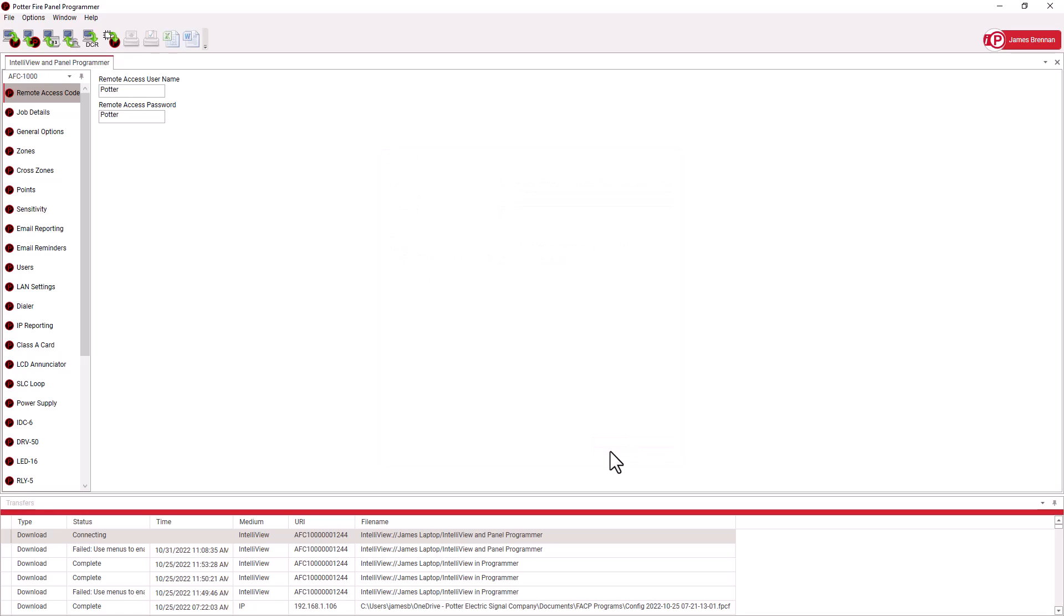Please keep in mind that this feature isn't intended for initial programming, since you would still have to perform some computer programming just to get the panel ready for IntelliView. This is meant more for adds, changes, and modifications to an already existing, programmed panel.